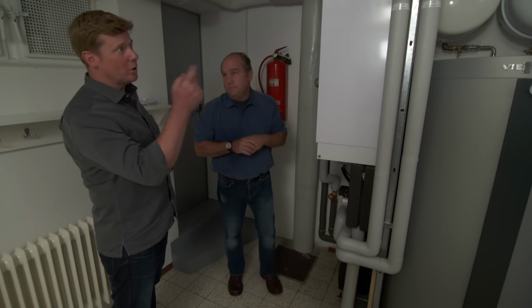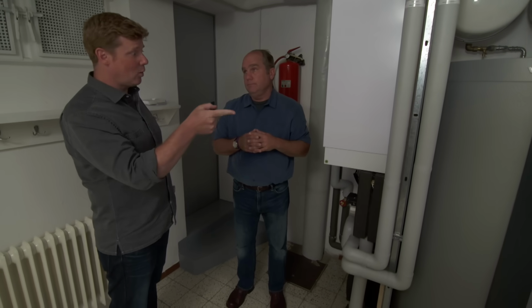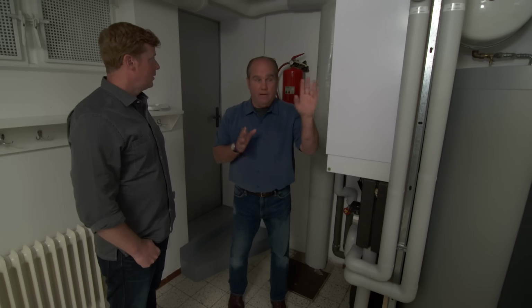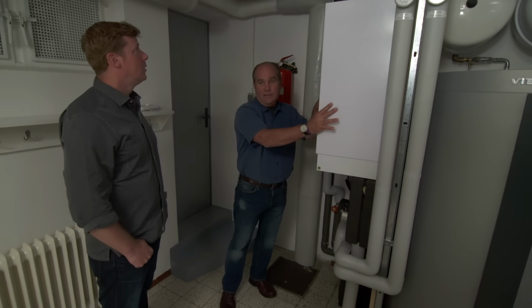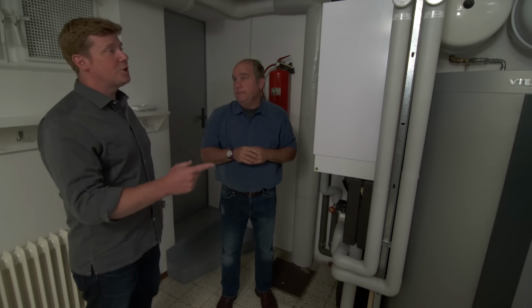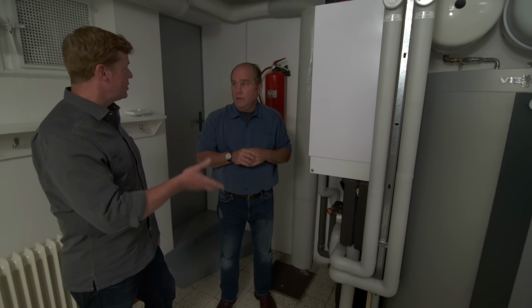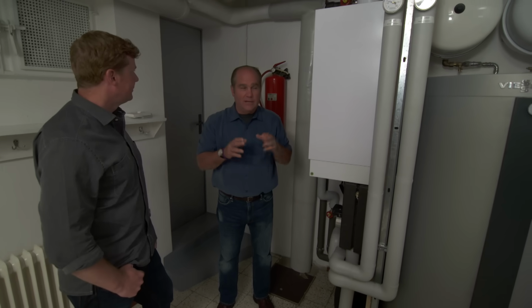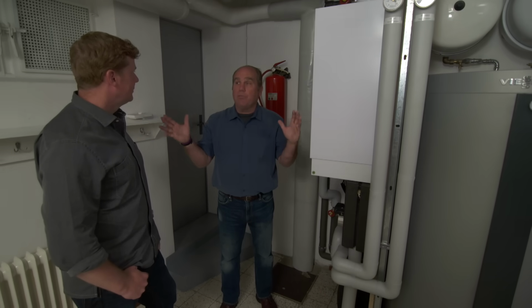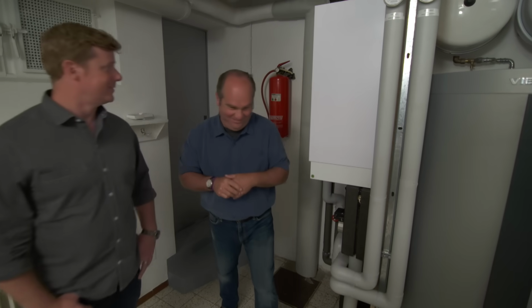So that's a small little box, and you said there's 10 units upstairs. That's right. Can that thing make enough hot water and heat for the entire building? It does pretty good. It's there, and if they need a boost, this boiler is here, but this only comes on about 7% of the time. It does most of the load. So the system makes electricity, hot water, and heat for the rooms. In terms of efficiency, where does it stack up? Really good. It's reduced the total energy footprint here between electricity and gas by about 30%. Wow. Paybacks in about 7 years. Oh, these Germans, they're into everything.